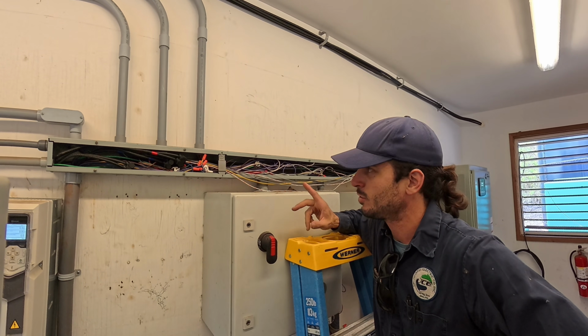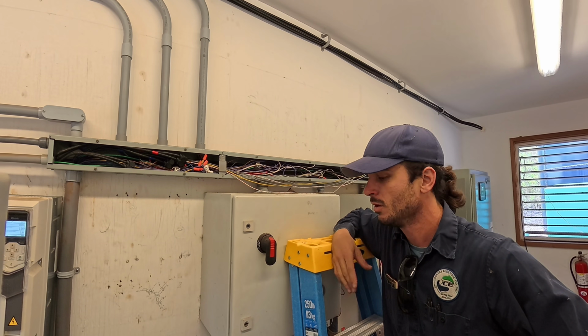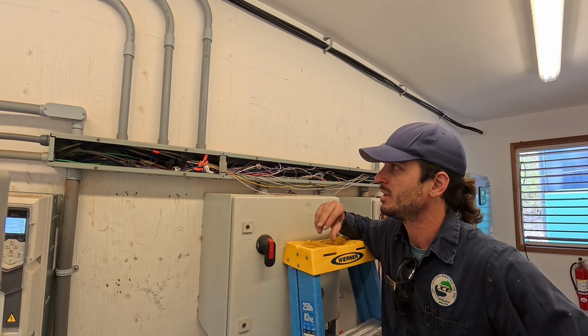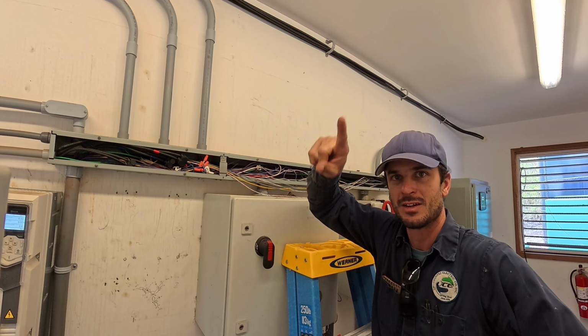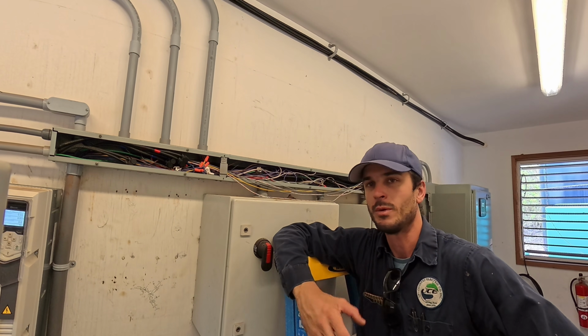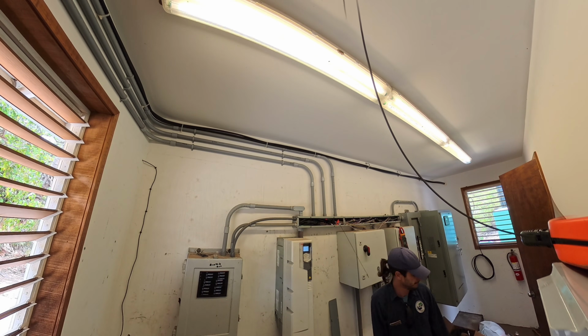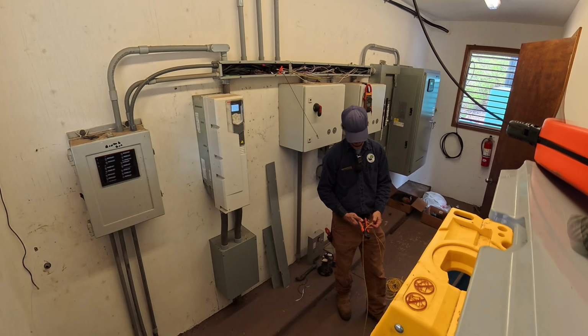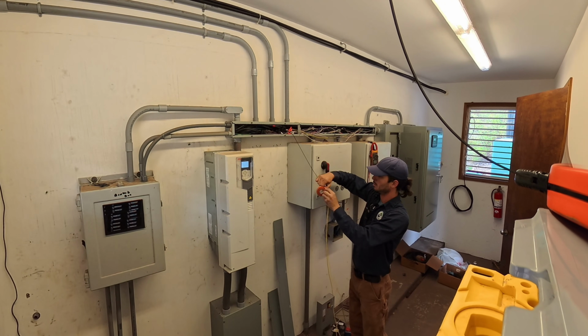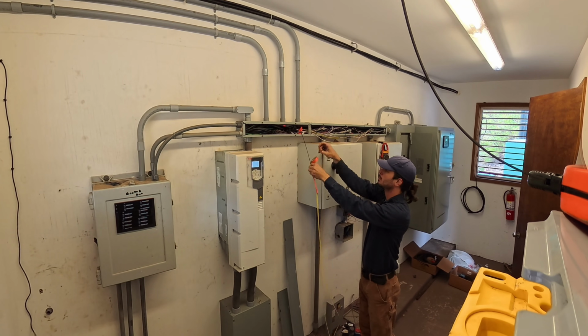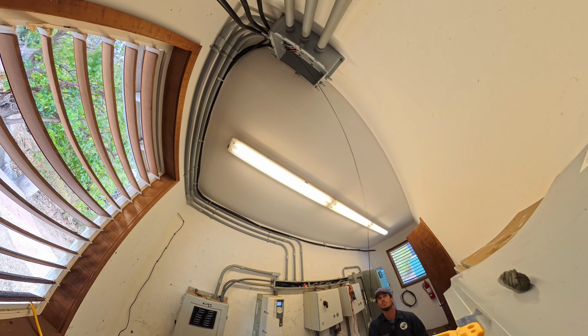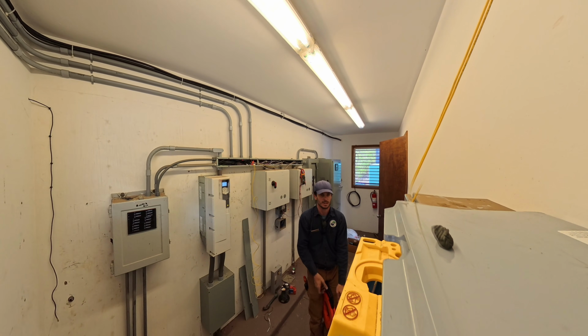So looking in this gutter, there's quite a few wires, but there aren't any spares running back to our controls. So what I'll do is pull a pair of number 18s from our starter back to the SCADA can and get them landed on a digital input. That way we can start testing. And get it in each end and land it and test it out.